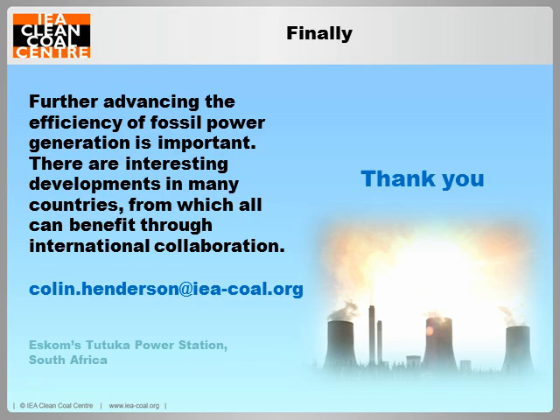I have a question here: do I have a feel for the economics of the upgrades, and which improvements are likely to be the most cost-effective? Most cost-effective depends on where you are, but basically the turbine improvements tend to be very cost-effective, certainly in the already fairly well-maintained plants, particularly in Western countries. To give you an idea of the sort of costs — how long is a piece of string — but a turbine retrofit might be of the order of 50 to 100 million pounds for a very large turbine system, though it can be less depending on how much is changed, and would be a lower price in a country such as India. A boiler retrofit would probably be 100 to 200 million. The turbine is probably the most cost-effective, if you can get a couple of percentage point improvements, certainly if you work on the condenser as well.